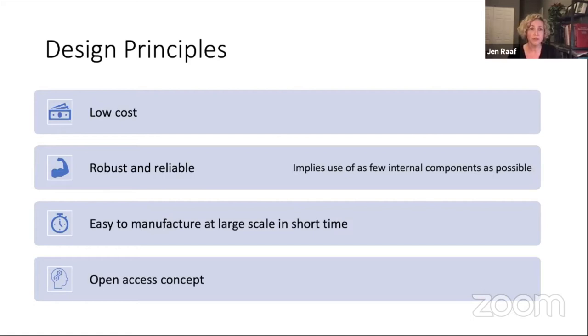Another thing that affects cost is parts. We were able to use almost all off-the-shelf commercially available parts, which also keeps the cost lower. In the end, the parts cost for our machine is around $5,000, and the total cost including manufacturing and technical support ends up being around $10,000—anywhere from 3 to 5 times cheaper than other commercially available ventilators.